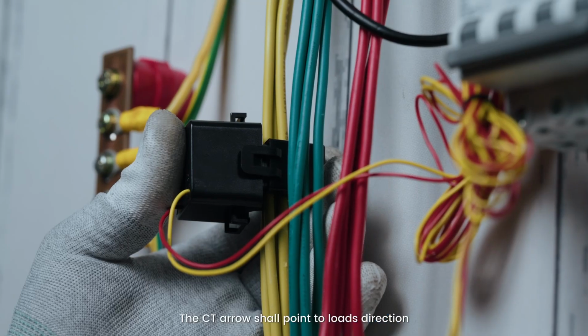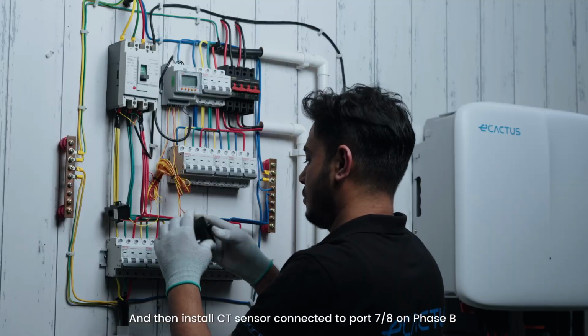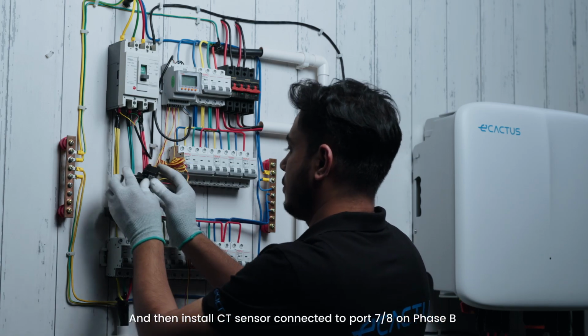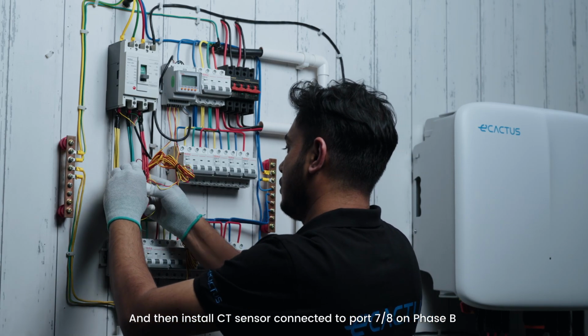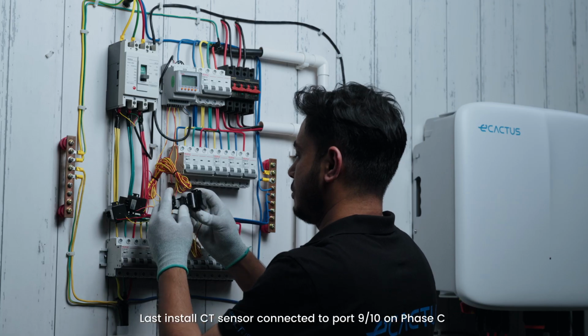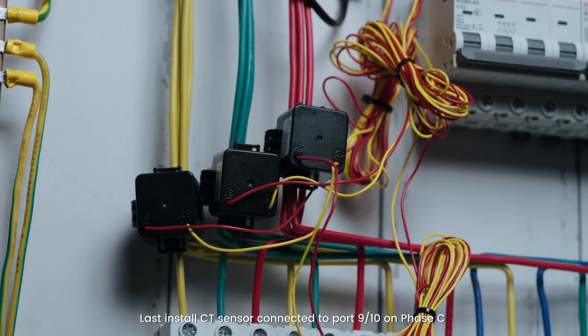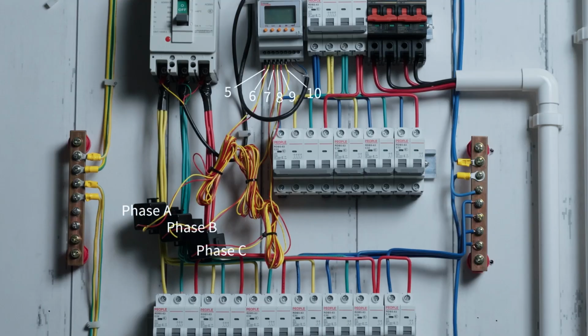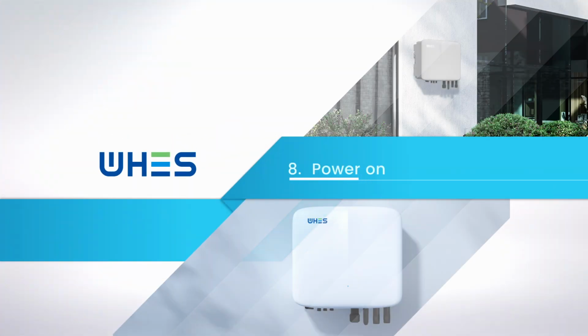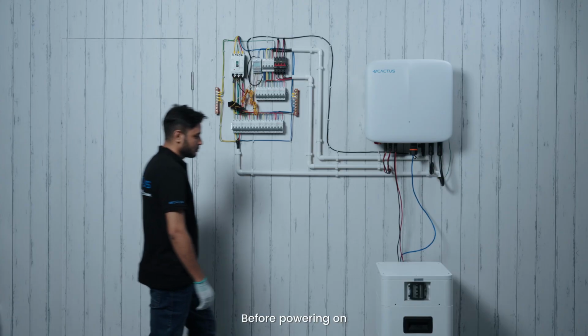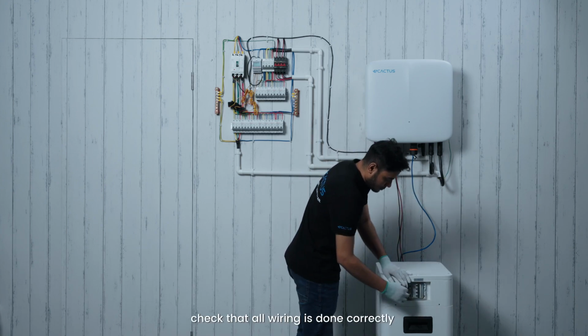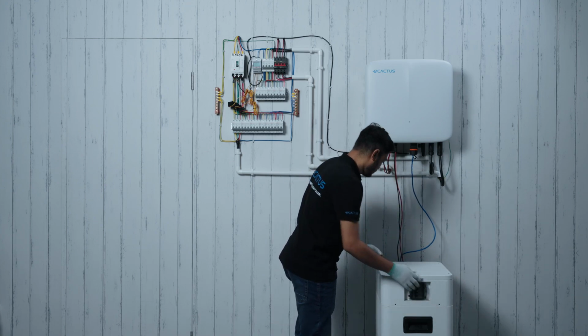The CT arrow shall point to load's direction, and then install CT sensor connected to port 7-8 on phase B. Last, install CT sensor connected to port 9-10 on phase C. Before powering on, check that all wiring is done correctly.